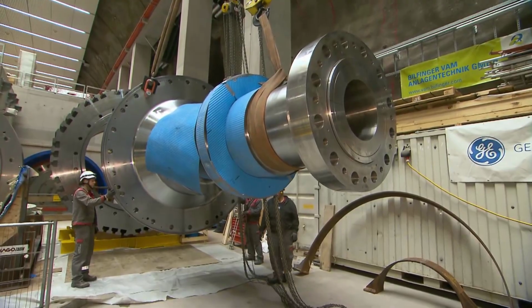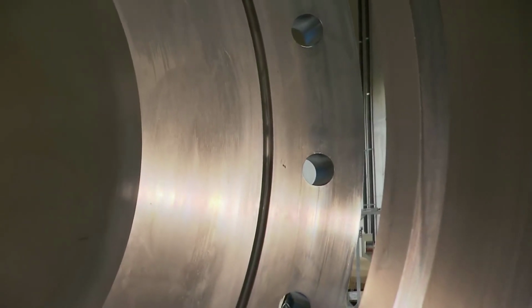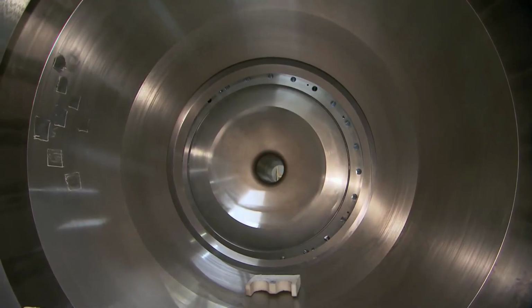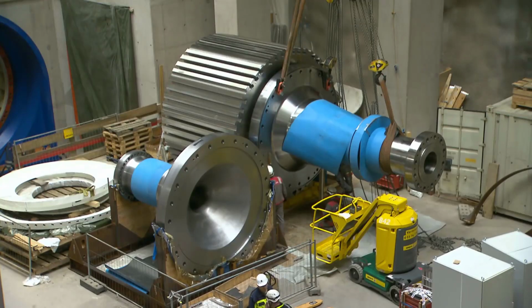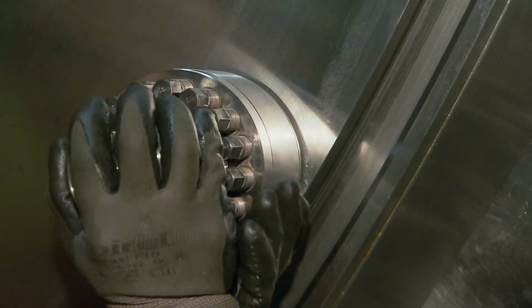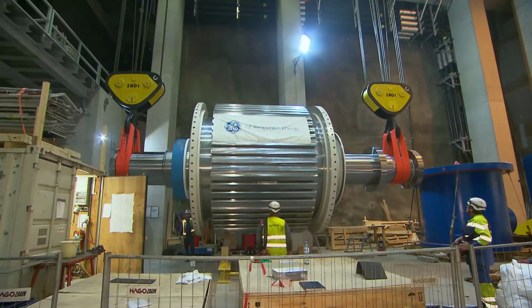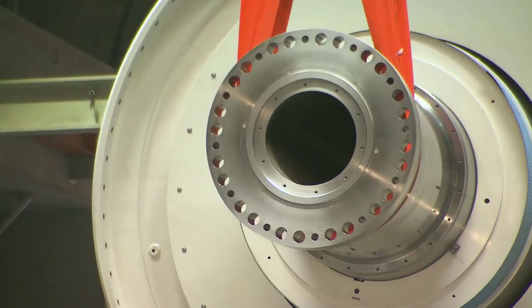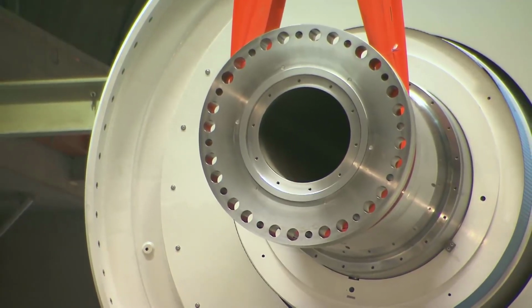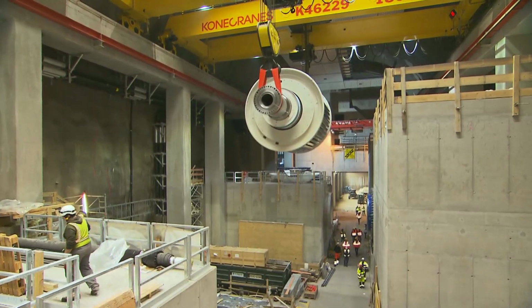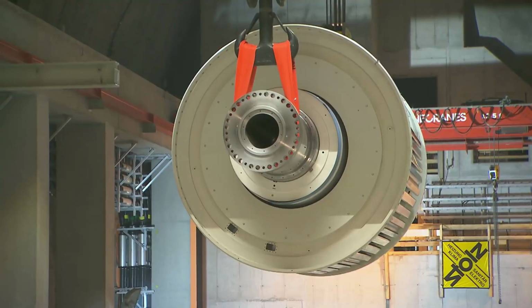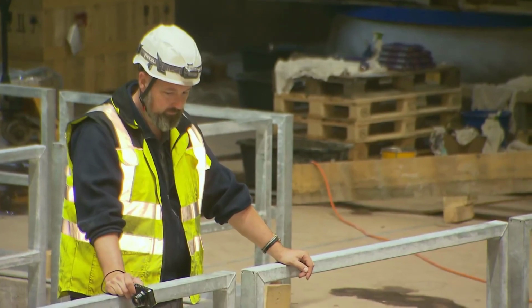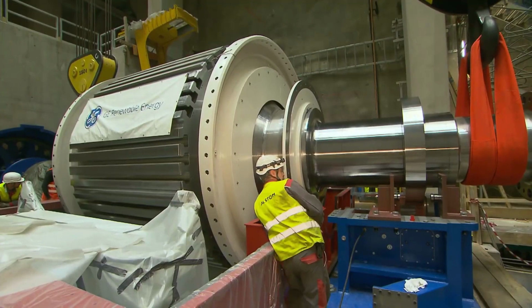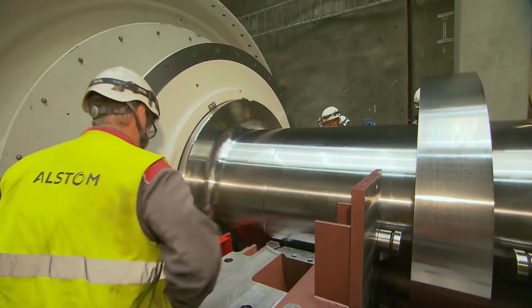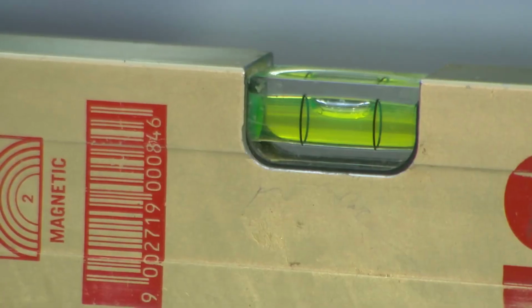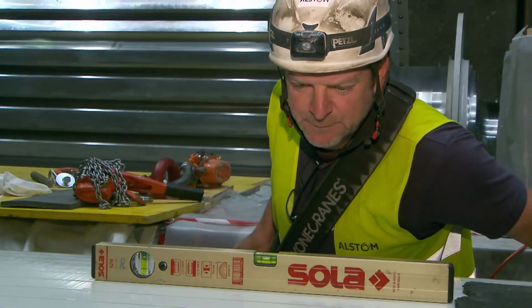One of the next steps is the installation of the 14 poles. The insertion of the poles, with only a 1 mm tolerance, is a demanding process. The poles must be perfectly aligned horizontally and brought to the correct height for installation. The poles now slide one by one into the rotor central body, where they are centrally aligned, wedged, and screwed. The finished rotor can be manually rotated for the first time, allowing checks on factors such as concentricity.